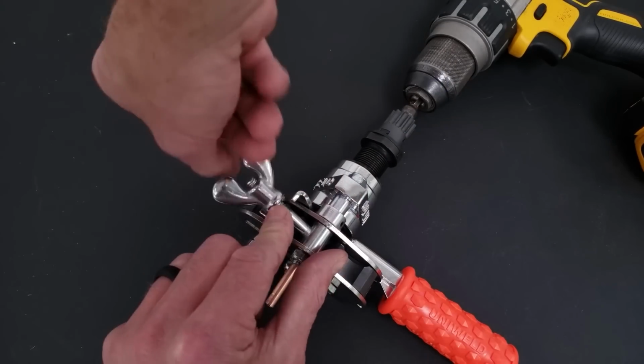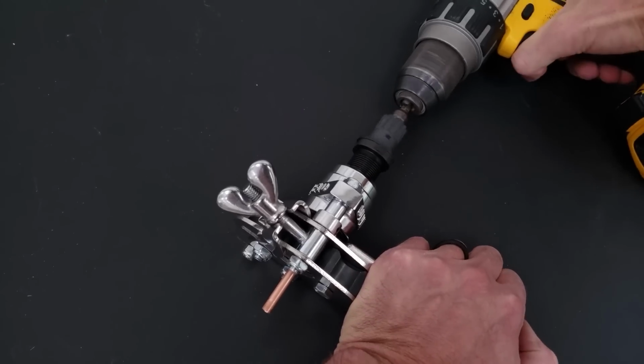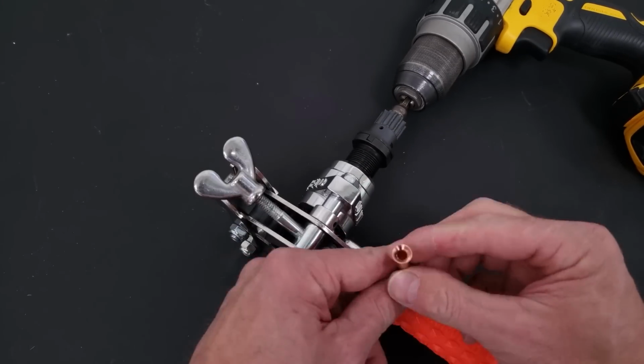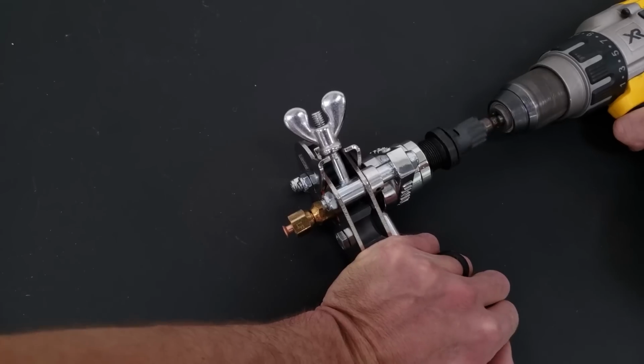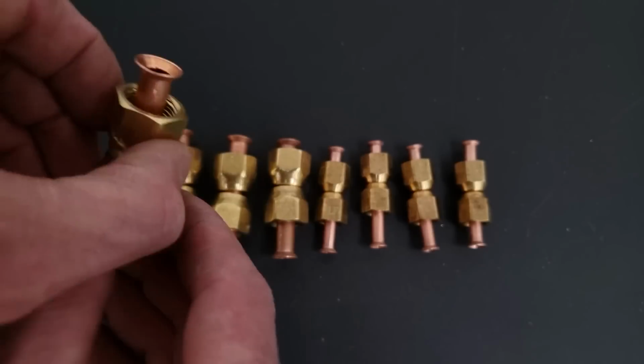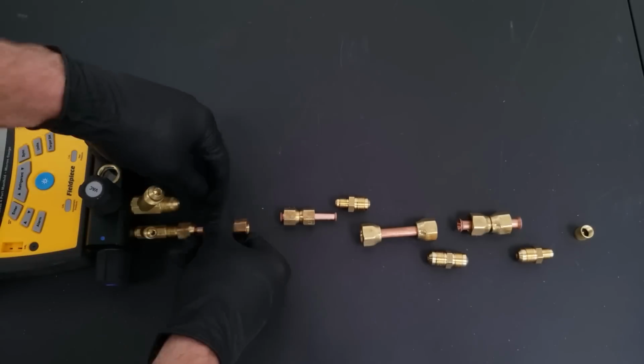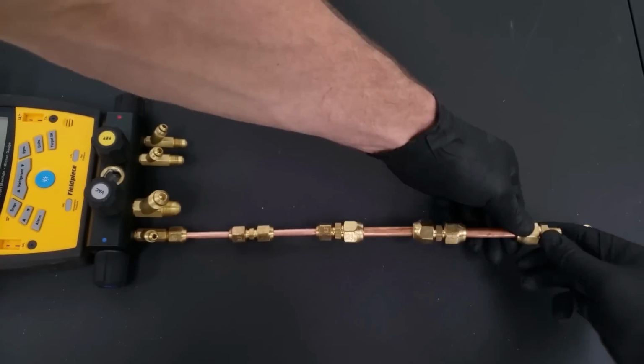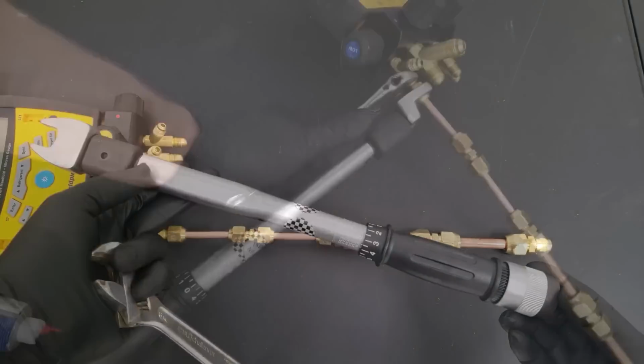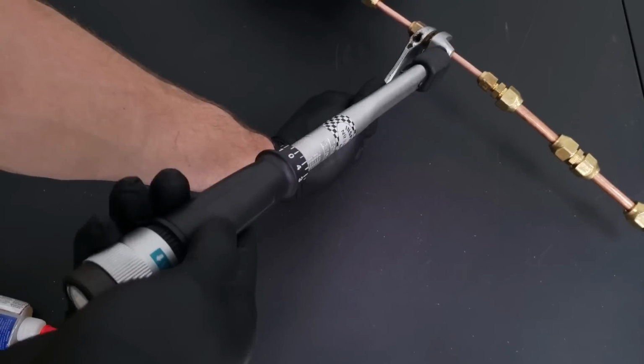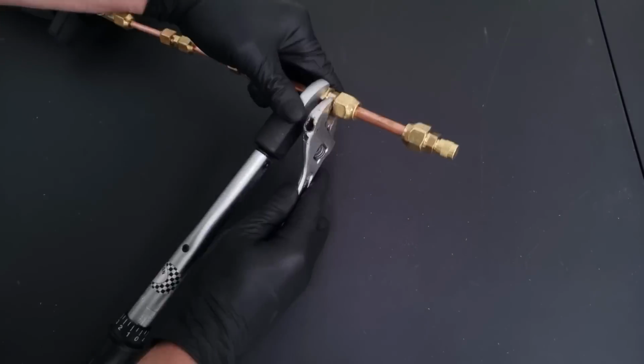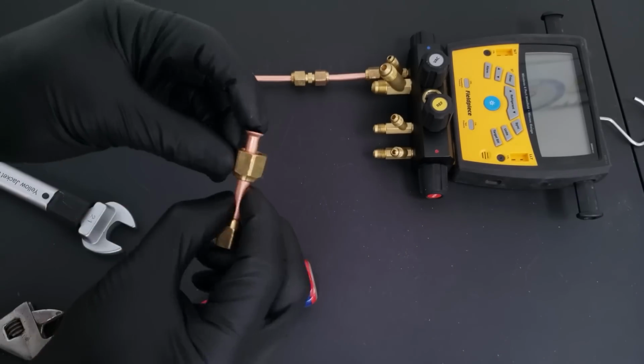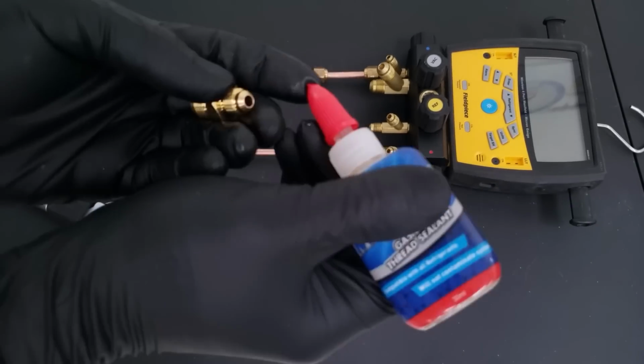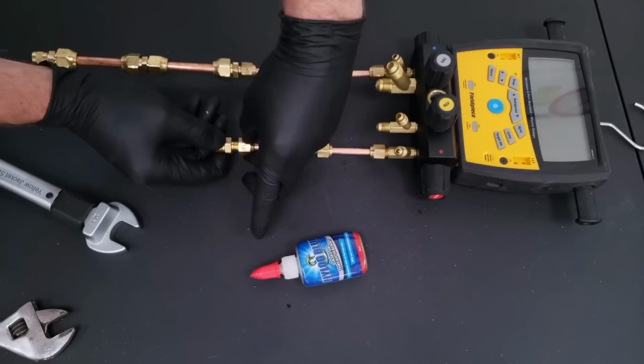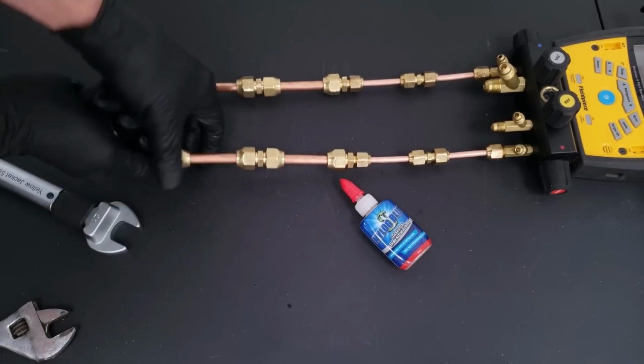I've also done experiments where it's just dry, just copper against brass, tightening it to the proper torque specifications, putting it up to 600 PSI, letting it sit, and seeing how much I can get the leak out over a one month period. And pretty good. I didn't really see any drops. I had maybe about 30 flare joints, just testing it, playing around with it. And I did a video on that, but I was kind of curious myself. I know everybody does them differently.